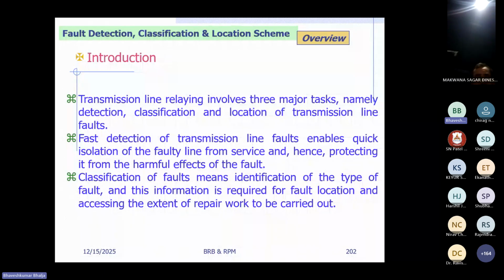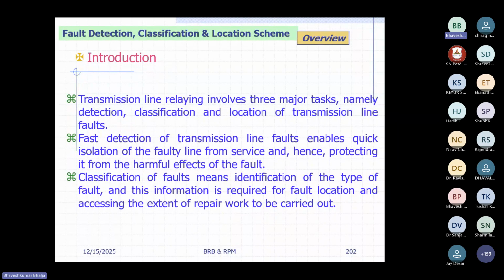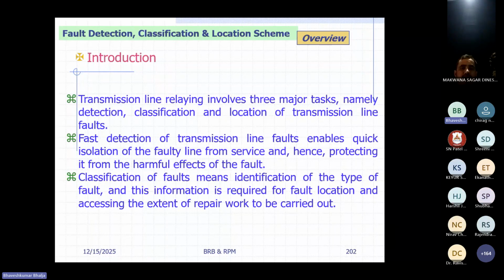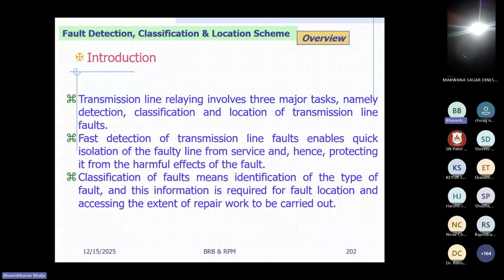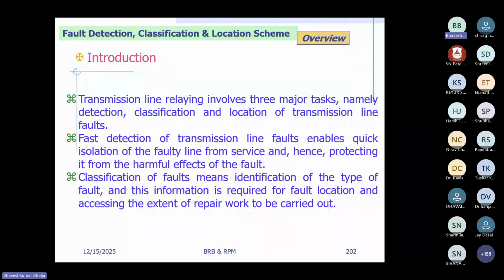Now how does the utility person know that, let's say, I have a 150-kilometer-long transmission line and a fault has occurred at 70 km, for example? We don't know, a fault can occur anywhere on the line. Now it has occurred at 70 kilometers. How does the utility person know that the fault has occurred roughly between 65 and 75 kilometers, with some tolerance or error? Because you cannot always find the exact location with a very precise value, so there is always an error.